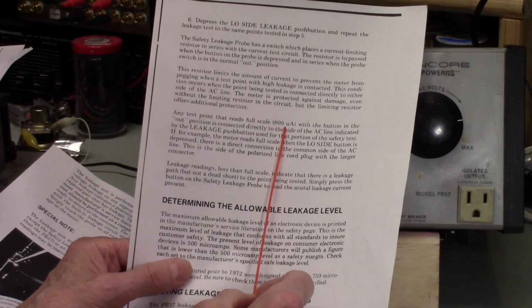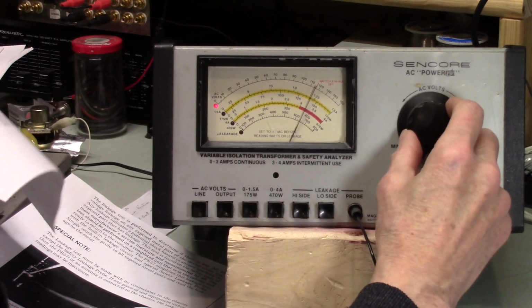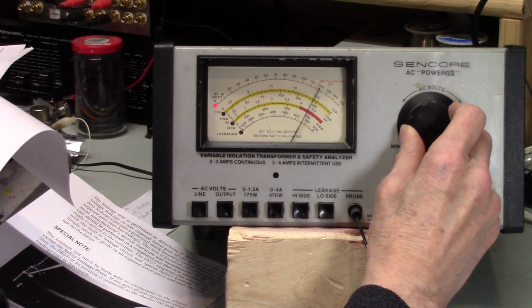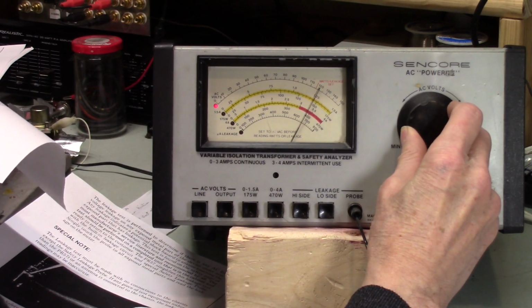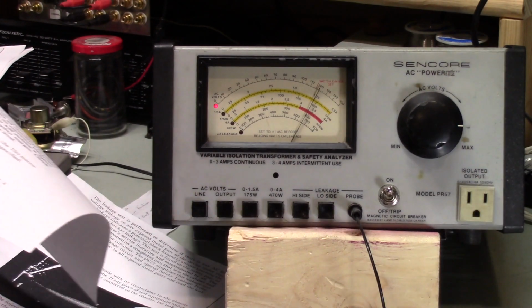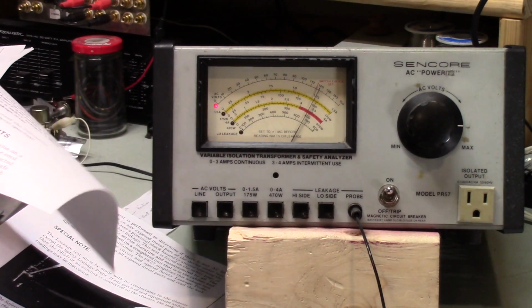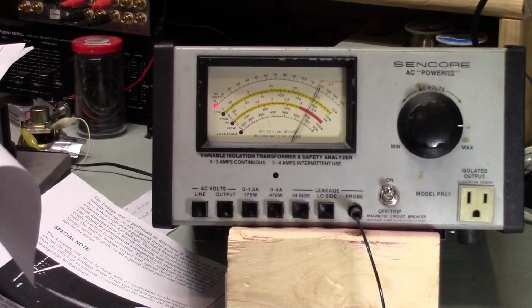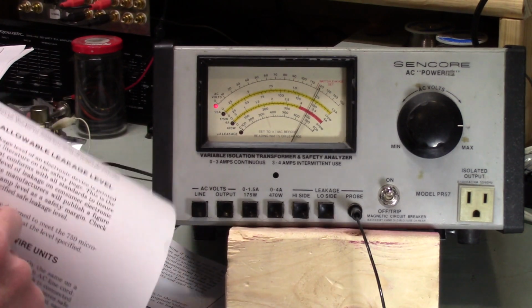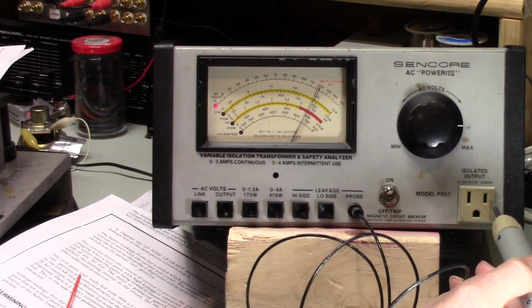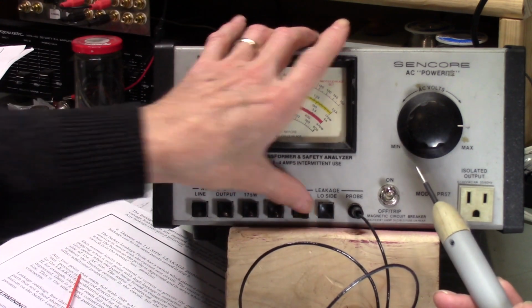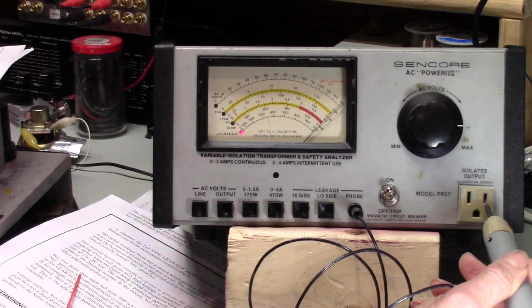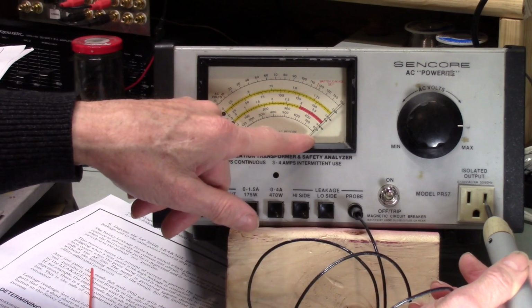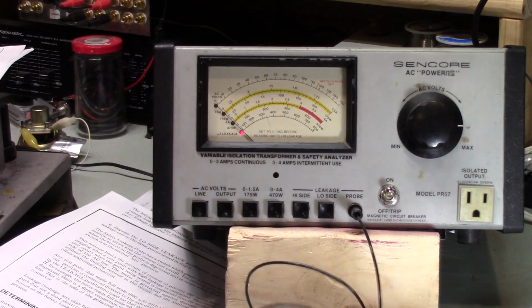The only way you can get an 800 microamp reading is if you bring it up to 120. My light is making a shadow so I can't see - go away. I guess it's alright, no matter. So I've got this at 120. Now watch, I push this in to the test point - high side, now we go there. And guess what? That is your 800 microamps.